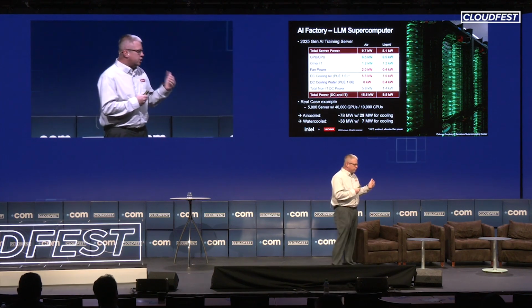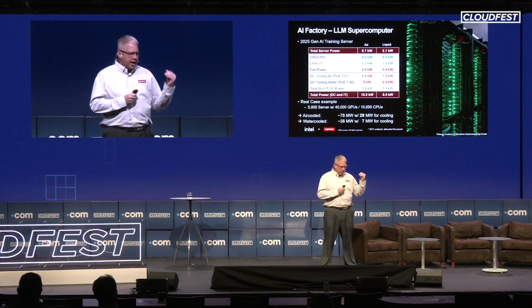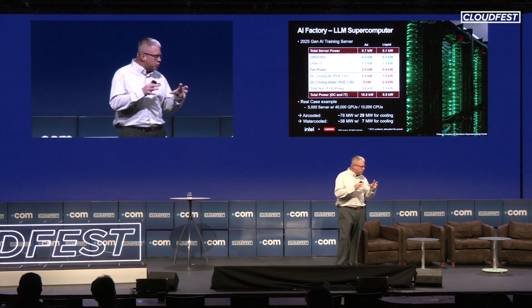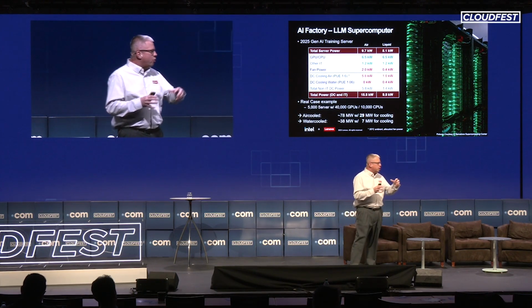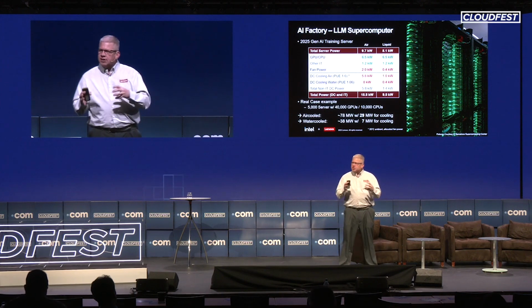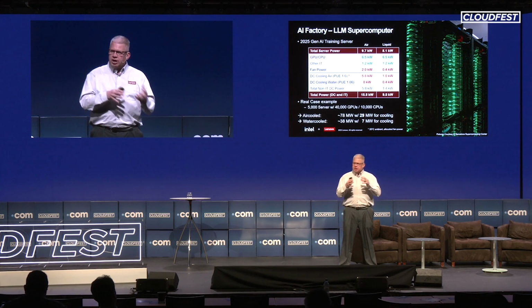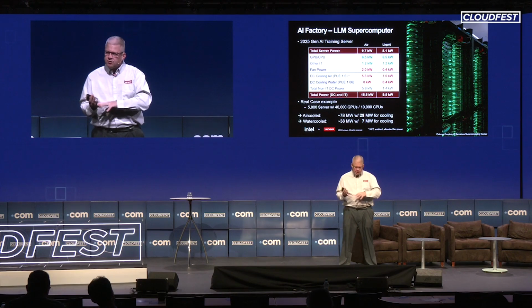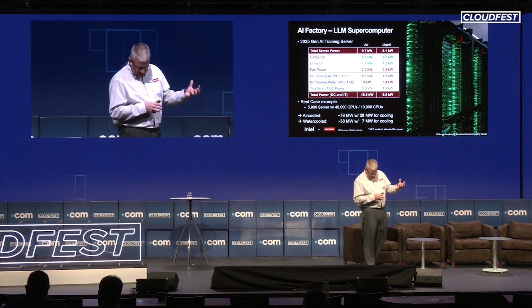So some real world solutions we've looked at from a customer perspective, comparing air versus liquid cooled - you've gotten all the way up to 78 megawatts for a deployment. You can see what the deployment looked like, with the amount of power to cool that around 30 megawatts. When you look at it from a liquid perspective, the savings from both the fan and the overall data center cooling takes that all the way down to somewhere around 40 megawatts, with about 7 megawatts of that for actual cooling.